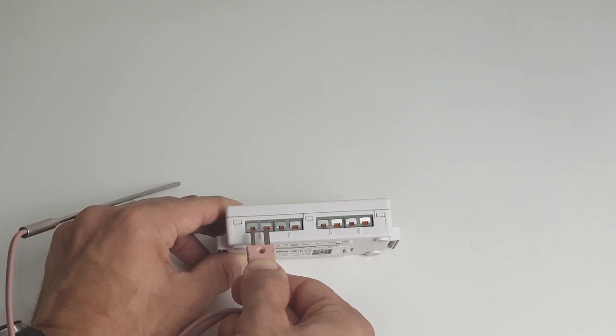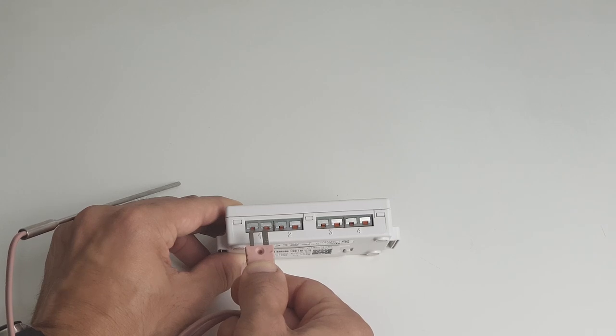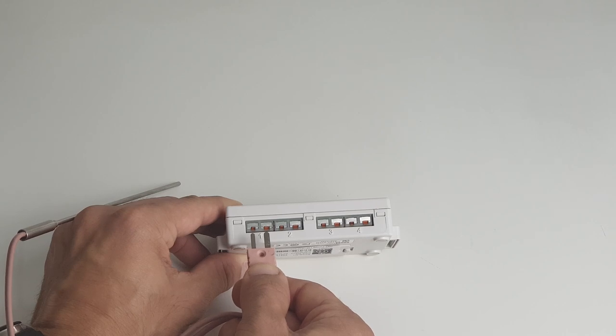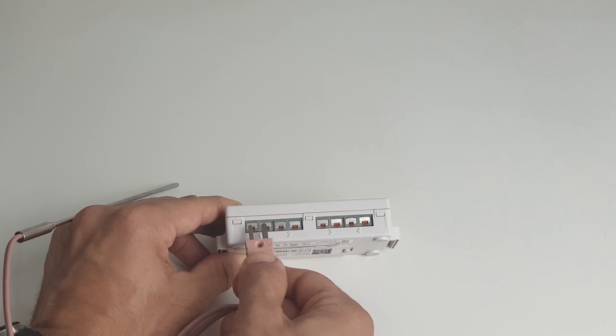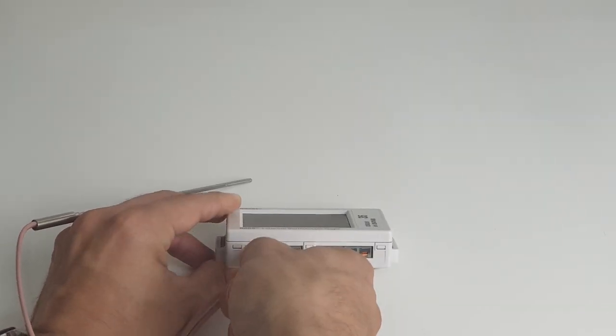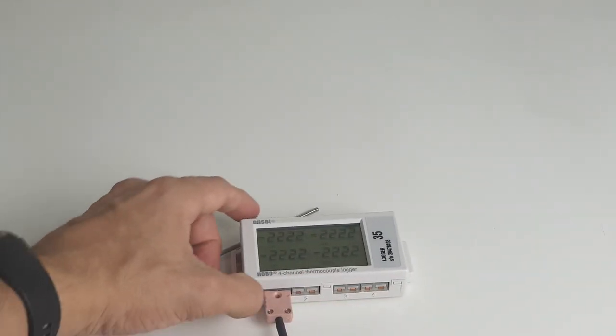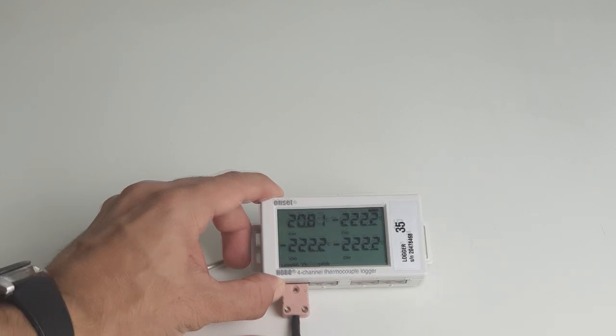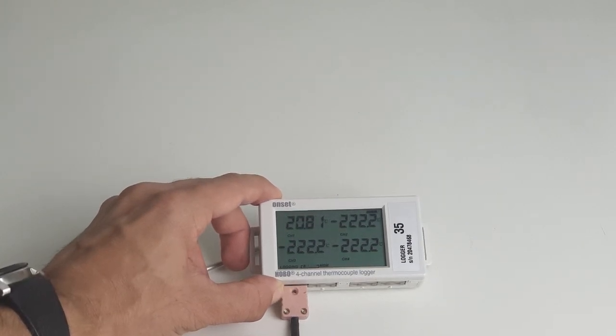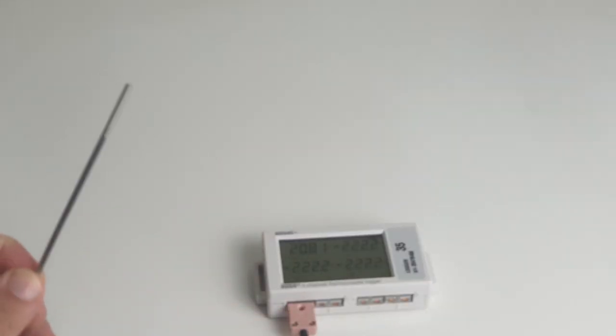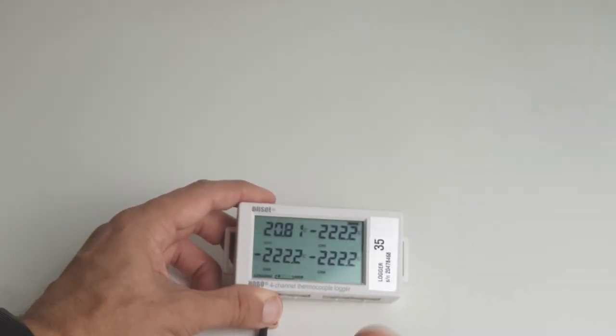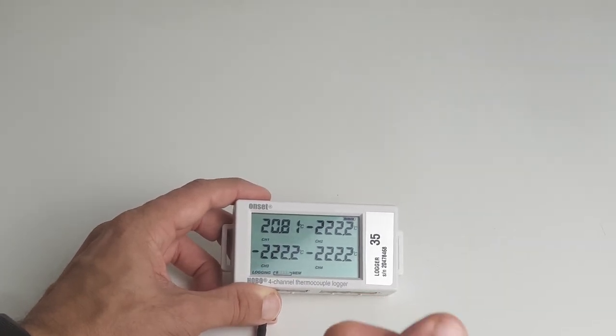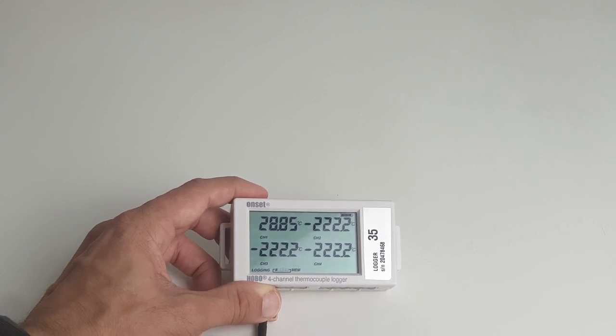What would happen if you did that is the readings would go in the opposite direction. If you plugged it in the incorrect way or had the wiring the wrong way around, when the temperature increases, the actual readings will drop. As you can see now, it's giving us a reading of 20 degrees Celsius. If I put my hand on the probe and start to increase the temperature, it's gone up to 28.85. So we now know we've plugged it in correctly and the wiring is fine.